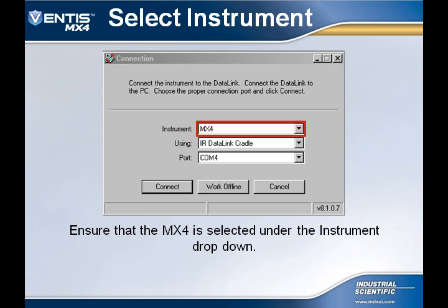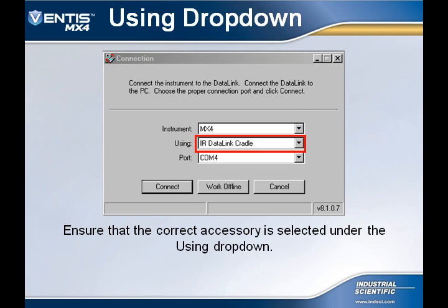Once the program has launched, double-check that the MX-4 is selected under the Instrument drop-down. Ensure that the IR data link cradle is selected under the Using tab. There are two options: one is for the infrared data link cradle, and the other is for the V-Cal station, which connects to the computer using a USB connection. In this example, we are using the infrared data link accessory. The V-Cal station will be described in further detail in module number 9 of this series.